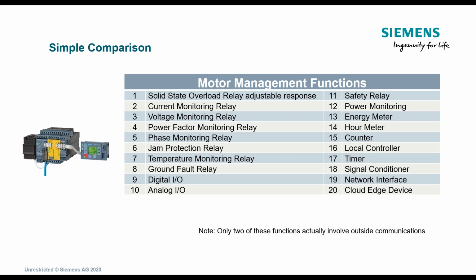They just wanted it to change direction. And so Westinghouse had an old jam module that you plugged into their overload contactor. If it saw the current get to a certain point, it stopped clockwise or counterclockwise and reversed the direction it was going. And that's what they needed. Well, Westinghouse no longer sold it, and they ran out of their eBay supplier, so they were looking to replace this system. SIMOCODE can do that for you. It has a jam protection module in it that is sitting there waiting for you to use.